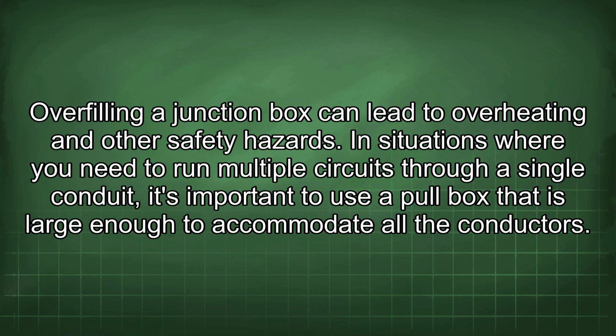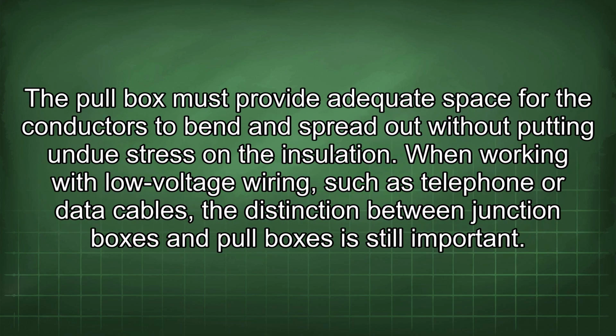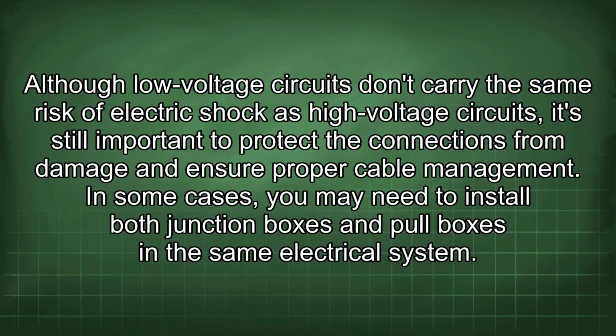In situations where you need to run multiple circuits through a single conduit, it's important to use a pull box that is large enough to accommodate all the conductors. The pull box must provide adequate space for the conductors to bend and spread out without putting undue stress on the insulation. When working with low voltage wiring, such as telephone or data cables, the distinction between junction boxes and pull boxes is still important. Although low voltage circuits don't carry the same risk of electric shock as high voltage circuits, it's still important to protect the connections from damage and ensure proper cable management.